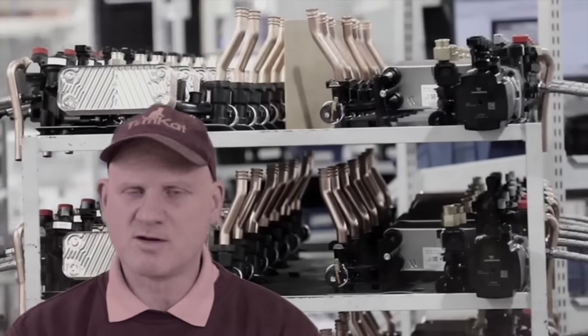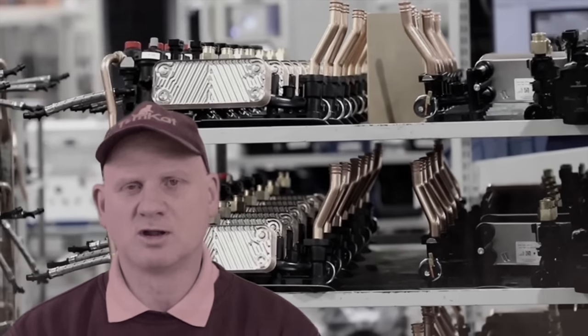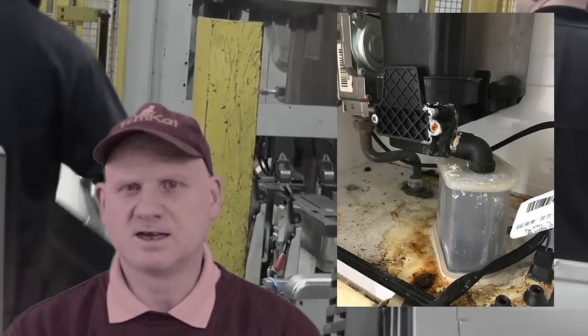Some years ago, Ideal had a lot of issues with a range of their boilers called the Icos and the Isar, which made Ideal go back to the drawing board, and they produced a new range of boilers called the Logic range. The Logic range itself has had a few issues with things like leaking sumps, which Ideal have now fixed, and Ideal now are competing for a major share in the market. Ideal have recently been taken over by French company Groupe Atlantic, and as the leaders in France for air source heat pumps, they see this partnership as a good strategic move for the company and their customers.